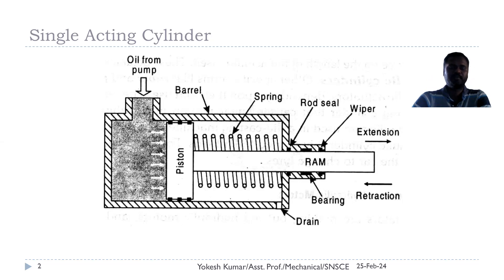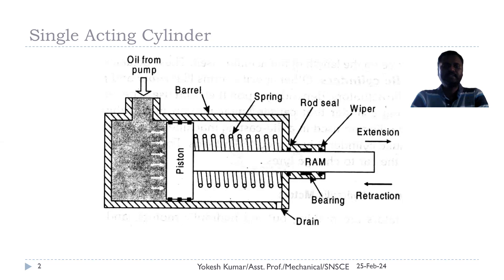Because the oil pressure is reduced — we are no longer connecting this port to the pump — the pressure automatically reduces in the blank end of the cylinder. Therefore, the spring pressure, being higher than the oil pressure, makes retraction of the cylinder. The oil is forced out via this port back to the reservoir. This is how the single-acting cylinder works.